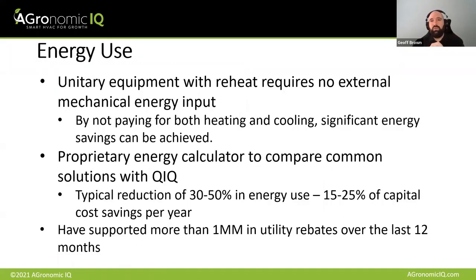Another factor, of course, is energy use. These facilities are energy pigs. It's something that everybody's aware of, but it matters. One of the biggest factors in terms of energy use for unitary equipment is that properly designed unitary equipment is able to use 100% of the compressor waste heat, so you've got the capacity to reheat for free, effectively. Anytime you've got a compressor operating, either in cooling or dehumidification, you've got enough energy in that system to make up all of your reheat. It means that you're not burning BTUs on both sides.